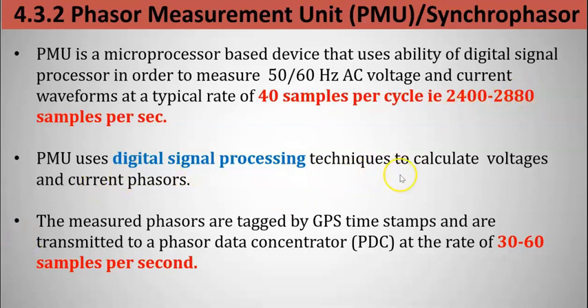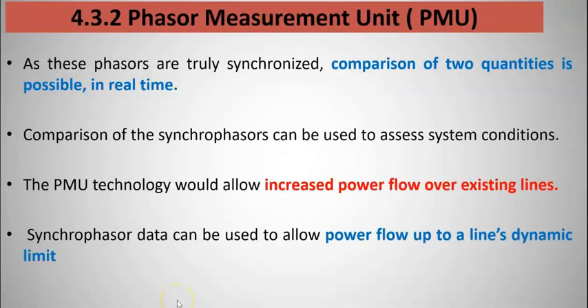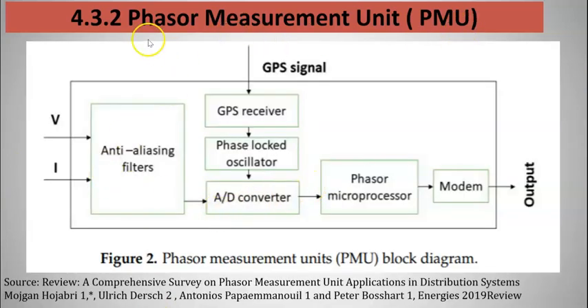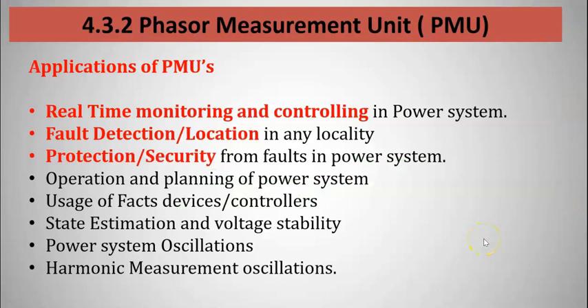PMU uses digital signal processing, particularly DFT. I use DFT also for signal processing. The PDC will collect that data and work at a rate of at least 30 to 60 samples, though this is also different in the latest systems. Two quantities will be compared - voltage and current, phasors and magnitudes. Basically the phasor measurement unit has GPS signals and filters, along with signal processing techniques and a microprocessor. I have not done hardware, but I use this PMU concept, the sampling, and that signal processing.